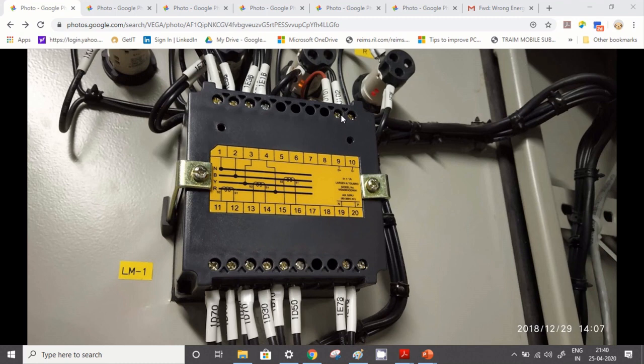So this is the basic troubleshooting which is possible in the L&T make Vega meter or any other make Vega meter, and in the same way you have to check the controller of the DG also, because there is also voltage sensing, current sensing, and also RS485 communication. So the same thing you have to try there, and I think if you try all these, there is a 95% success ratio that your meter will become healthy and it will start communicating.